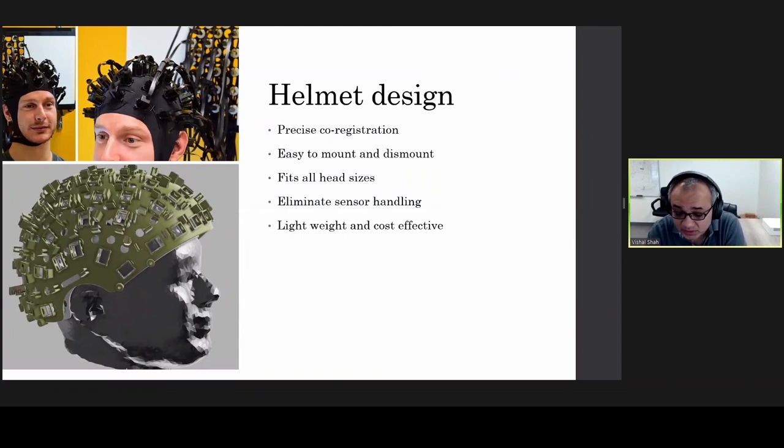Another key aspect of the technology that we, and also a number of other research groups, really are working on, is developing an advanced OPM helmet. And this OPM helmet, it really needs to meet several criteria. For example, the helmet has to provide precise coregistration data, which is where the sensors are placed with respect to the head. It should be very easy to mount and dismount, so that the subject preparation is almost non-existent. It should fit all head sizes, so that you can scan not just adults, but also children of any age. Hopefully it eliminates all kinds of sensor handling, to improve the system longevity. And the helmet should be very lightweight and should be cost effective.